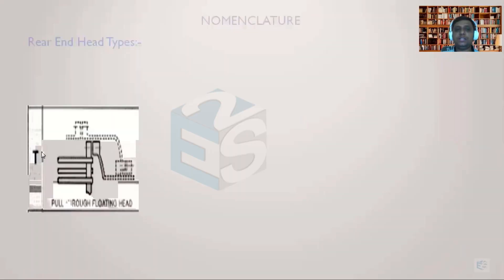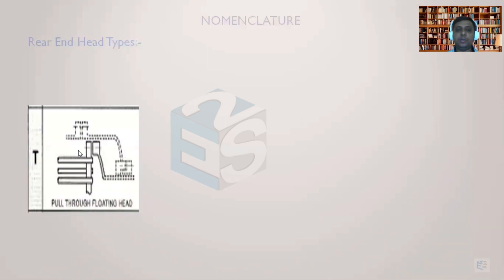The next type is called a T-type. It is also an internal type of floating head like the one we have seen in the case of the S-type heat exchanger, but the difference here is that there is no backing device. The tube sheet itself will extend as a flange, and the floating head will have a flange, so they will be tightened against one another. This entire assembly can be removed. The basic disadvantage of T-type over S-type is as follows.